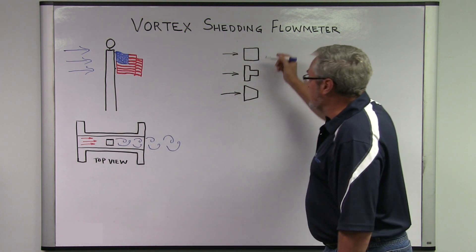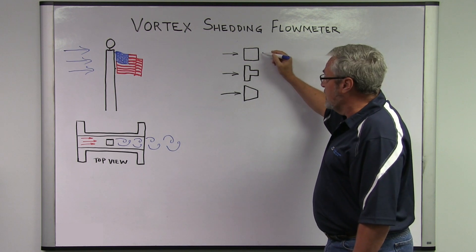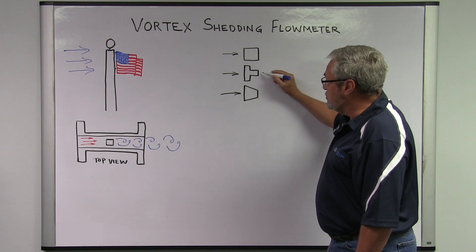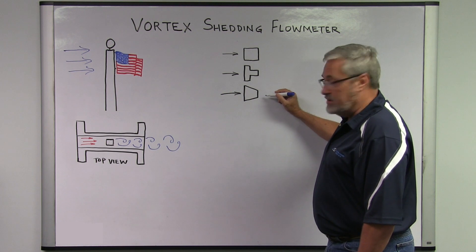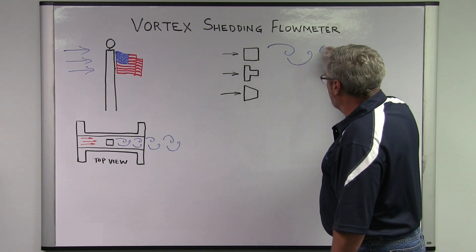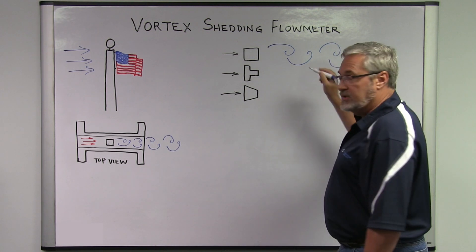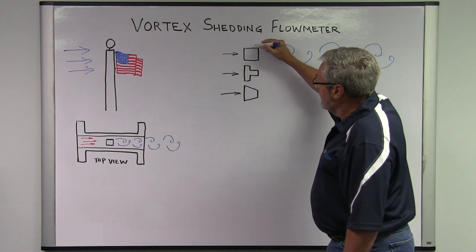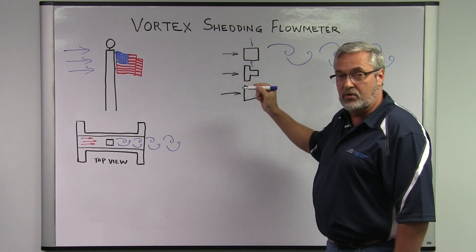Common shapes of a shedder bar include a square piece of stainless steel, a T-shape, or a trapezoidal shape. The shape doesn't matter so much, as long as it will generate these high and low pressure zones downstream based on a certain range of Reynolds numbers, causing the shedder bar to move from side to side and generate those vortices.